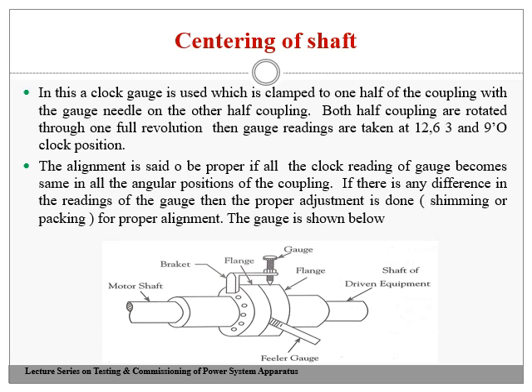That is, I am going to rotate this clock one revolution. I'll take down the readings of the gauge at the 3 o'clock position, 6 o'clock position, 12 o'clock position and 9 o'clock position. The alignment is said to be proper if all the clock readings are the same. The alignment is said to be proper and centered. That is, all the readings are the same at 12 o'clock, 6 o'clock, 3 o'clock and 9 o'clock positions. If they are the same at all the positions over the whole revolution, then I can say that the shaft is centered properly. This way we can do the shaft alignment for an induction motor before coupling.